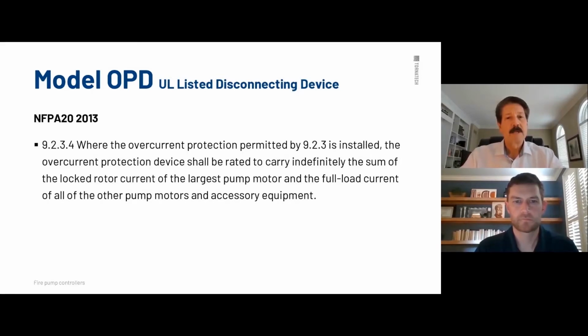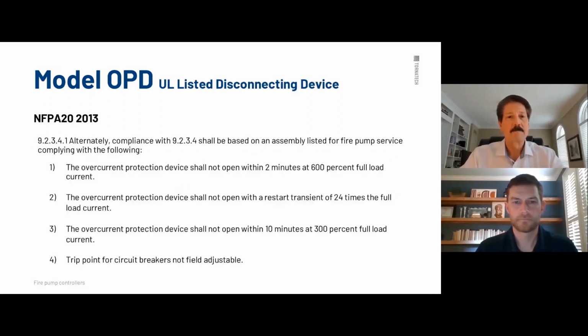9.2.3.4. Overcurrent protection permitted by 9.2.3 is installed. The overcurrent protection device shall be rated to carry indefinitely the sum of the lock rotor current of the largest pump and the full load current of all the pump motors and accessory equipment. In essence, what we're running across here in most cases, it's really the fire pump and the driver of the motor itself. That's what we're talking about here. 6 times full load amperage, locked rotor.